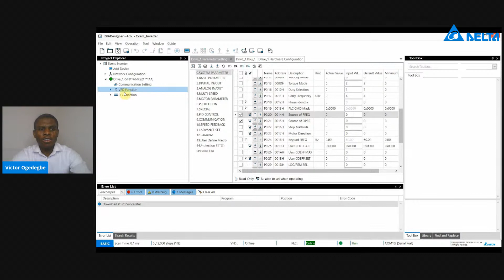Let's disconnect. One of the features that this offers to you is the flexibility of using the interface of your choice to program your inverter. So you could choose to use Communication Manager, our famous COM manager, communication driver. You could choose serial ports. You could choose Ethernet. So the choice is yours. And once you have chosen your interface, with one cable, you can program both the internal PLC and the parameter of the drive at the same time.